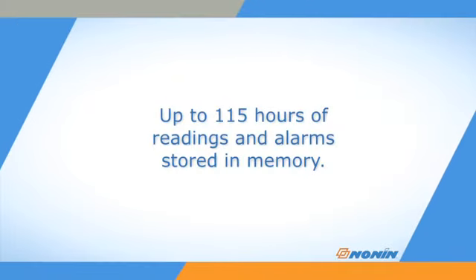The oximeter will record the time and date of any alarm in its stored data, along with regular oxygen saturation and pulse readings for at least 115 hours of data. It overwrites data when the memory space is full.